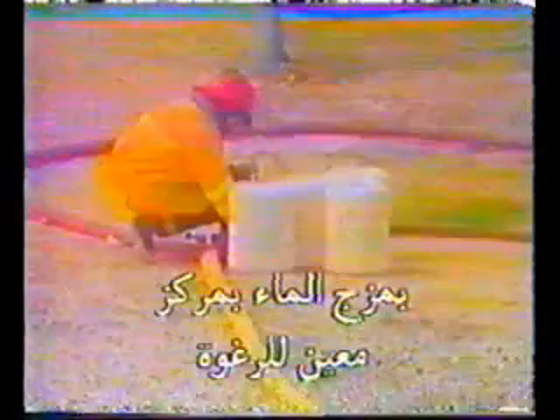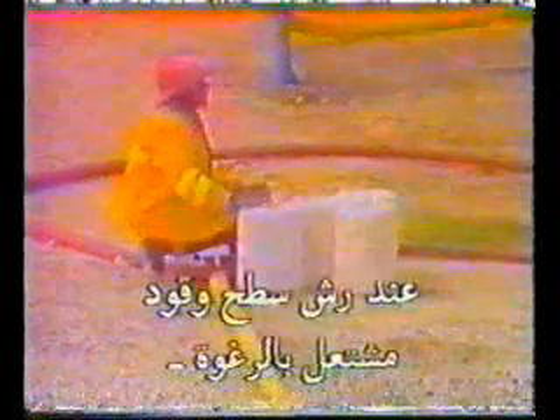Another important firefighting agent is foam. Although there are several different types of foam, all of them are made up by mixing water with a special foam concentrate. When foam is properly applied to the surface of a burning fuel, it forms a vapor seal. This seal prevents air from reaching the fuel, and also prevents fuel vapors from reaching the fire. Because foams are made with water, they also cool the surface of the fuel.